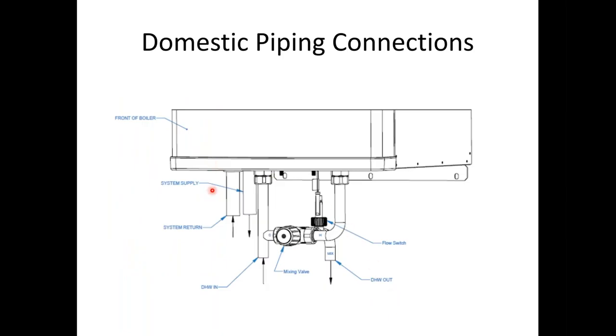Your domestic hot water connections will be right there on the bottom: your domestic hot water in, domestic hot water out, and then your mix leaving. It'll fit right underneath. The mixing valve is already in there, and they're all sweat connections. You can press right to it. I would suggest maybe putting unions on it so you're able to drop it down to flush it.